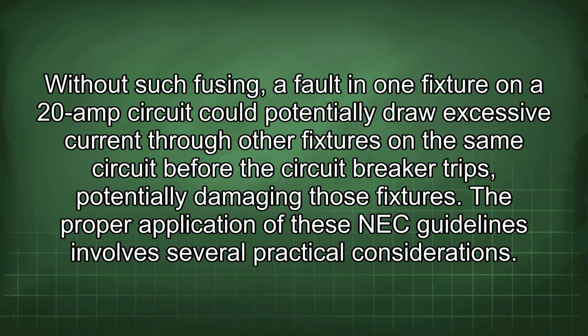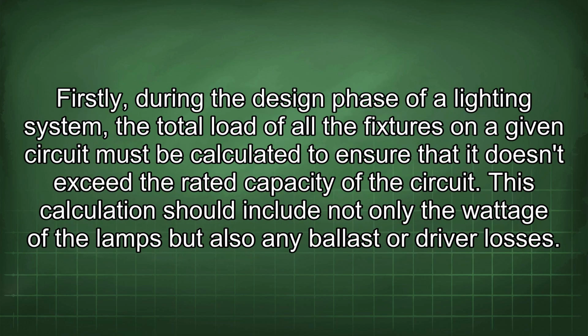Without such fusing, a fault in one fixture on a 20 amp circuit could potentially draw excessive current through other fixtures in the same circuit before the circuit breaker trips, potentially damaging those fixtures. The proper application of these NEC guidelines involves several practical considerations. Firstly, during the design phase of a lighting system, the total load of all the fixtures on a given circuit must be calculated to ensure that it doesn't exceed the rated capacity of the circuit. This calculation should include not only the wattage of the lamps but also any ballast or driver losses.